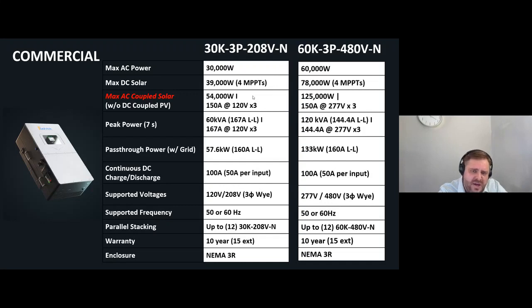So if you already have existing solar and you've done the cover-the-rooftop philosophy on a commercial site, let's say you only do commercial Solar Edge, but you want to add batteries to that commercial Solar Edge project, you can go and click on a Sol Ark 60K, and that can have up to 125 kW AC coupled solar array that lands directly onto its controlled gen port. On top of that, if you added a 250 kW array, you could do it with as small as 2 Sol Ark 60Ks, and that would give you 250 kW of AC coupling, and 120 kW of demand management, net metering export capability, or backup power capability, however you see fit.